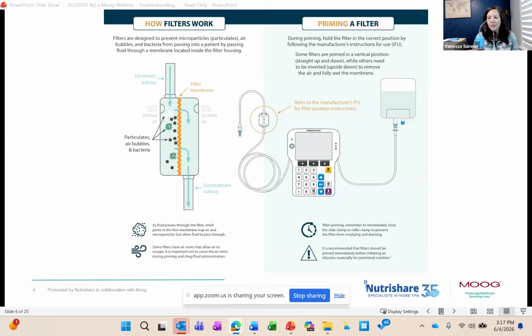And this can occur when you raise the air eliminating filter above the patient's catheter entry point. So if I were to, I don't have my slide clamp on, my slide clamp is nice and open. If I raise my filter up, I have to raise it a little higher here, it will start to empty. You may have had this happen before. You prime your filter, you prime your tubing, and then you start putting everything together, getting ready. And then you come back and you notice your filter is empty. You might be able to see it. Mine's starting to empty.